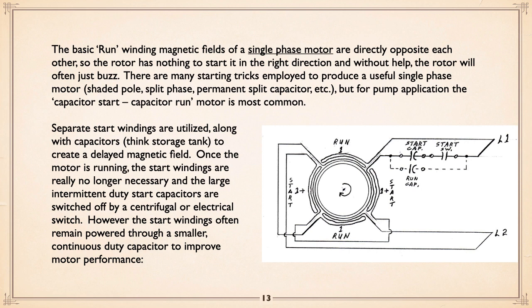If it's buzzing, one of the tricks you can do on a small one is go over and just grab it and turn it by hand quickly the direction you want. It'll catch it. Now it knows which way to go, and it'll start running. It's like a toy steam engine. You have to tell it which way to go by flipping it. So what you end up doing is putting in a start winding and then using capacitors to delay the power so that first, like at the top, the very top one is being energized. Then with a slight delay, the one to the right is being energized, and then the other direction, and that gives us rotation clockwise.